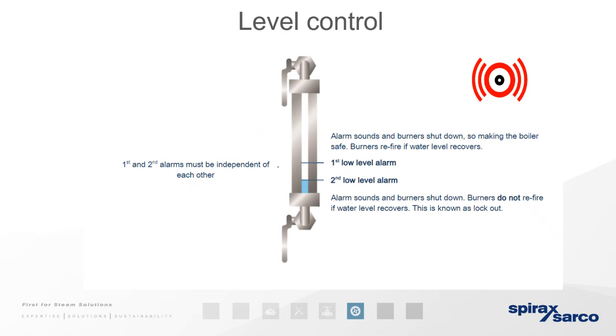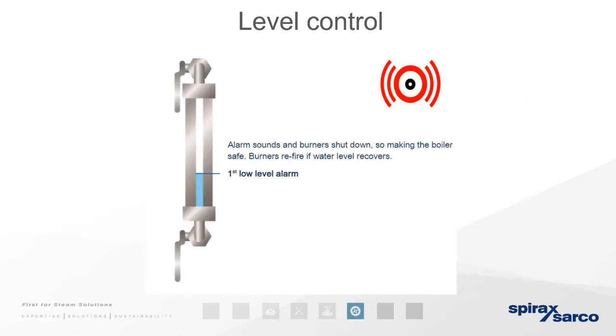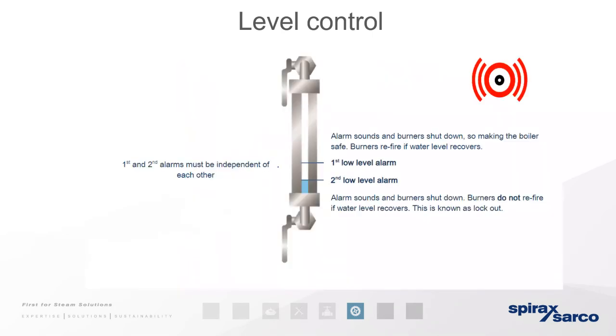As it says here, if you reach the second low alarm, the burner locks out and won't fire, even if the water level recovers. What I probably should have said there is that at first low, if the water then starts to rise because your pump kicks in, the audio alarm will stop and the boiler will turn back on. Second low means the burner will lock out, and even when the water level returns to where it should be, you have to manually reset. That's very important. It's protecting the fire tubes and the pass tubes in your boiler from overheating and potential collapse. So these are very important controls.